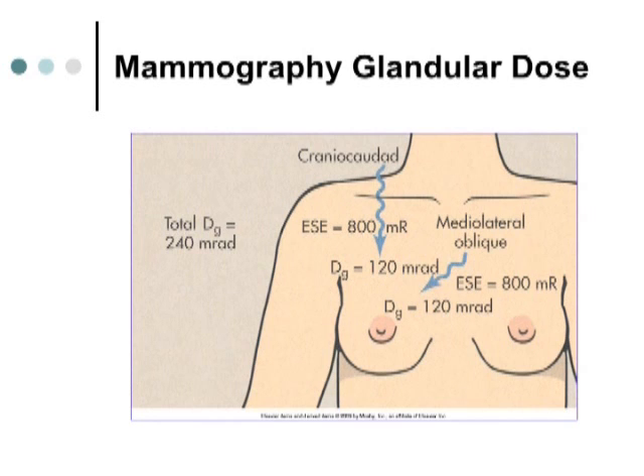The dose with digital mammography has been greatly reduced. A screening mammogram takes two views — cranial caudal and medial lateral. On the CC view, there's about 800 millirads entrance skin exposure, but actual glandular tissue dose is about 120 millirads — equivalent to about 12 chest x-rays. The reason dose is relatively high is that mammography uses very low KVP and high mAs to get contrast in a body part with very low subject contrast. The total dose to each breast in a typical mammogram is about 240 millirads.